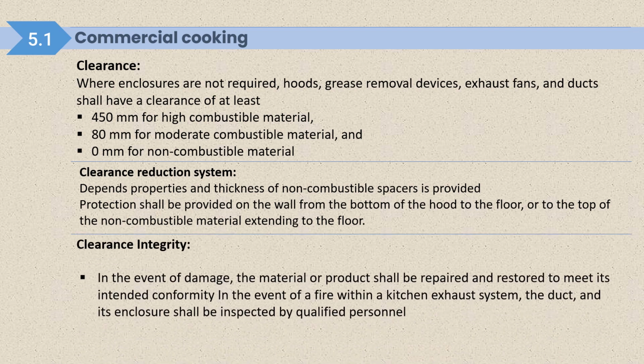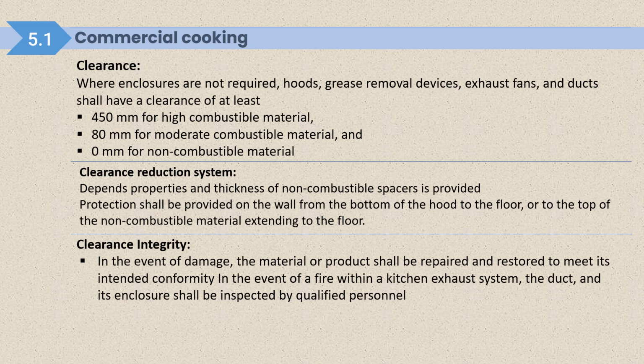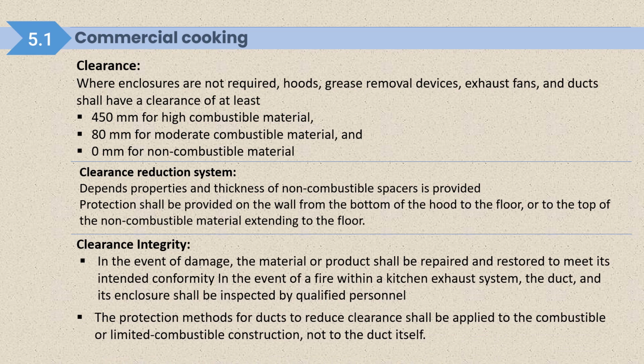Clearance integrity. In the event of damage, the material or product shall be repaired and restored to meet its intended conformity. In the event of a fire within a kitchen exhaust system, the duct and its enclosure shall be inspected by qualified personnel. So if you observe any type of damage, the material or product shall be repaired and restored to meet its intended conformity, and it should be inspected by qualified personnel. The protection method for ducts to reduce clearance shall be applied to the combustible or limited combustible construction, not to the duct itself. It doesn't mean you protect the duct; you are protecting the combustible material.